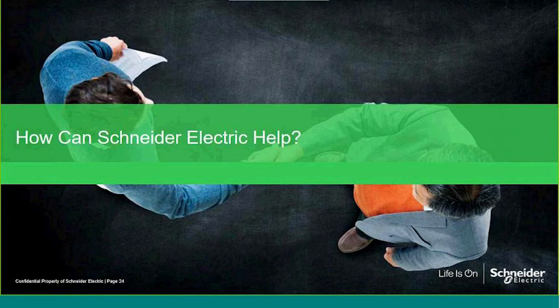So that's really an introduction to the arc flash subject matter. As I've said, whilst it's not a piece of legislation, it's another piece of the jigsaw, along with the fault levels on the network and the protection clearance times on the network, for you to really understand the risks that you are exposing yourself and employees to at that point in the network. As I say, it's okay going forward with brand new equipment, but a lot of our equipment is 25, 30 years old. We really don't know. We're not quite sure of its condition. We're not quite sure how it will contain arc flashes. And therefore, if there's any doubt in any shape or form, this is a really good exercise to understand the risks and to try and mitigate any exposure to those risks at that substation level.